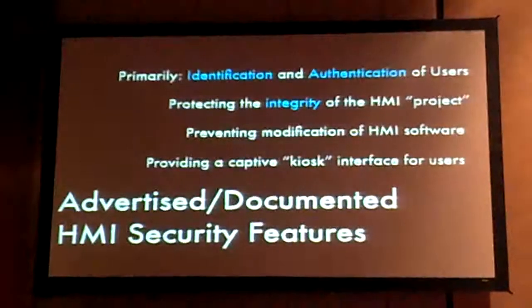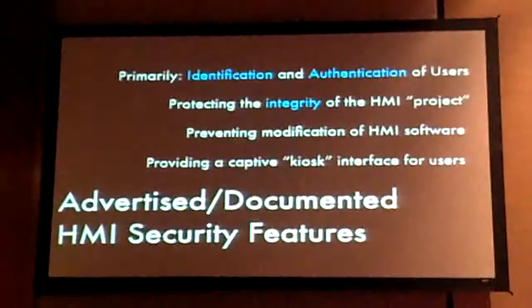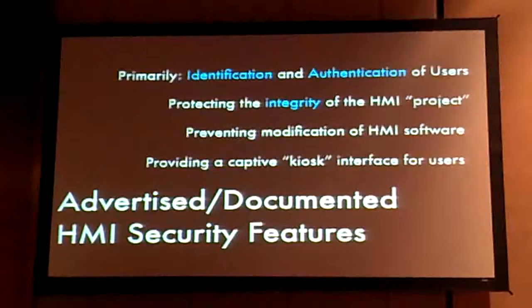But there are a lot of packages that claim some security functionality. Primarily, the security functionality advertised by these products is the identification and authentication of users. There are complex systems for having multiple layers of access — different access levels — from the operators sitting at the control panel all the way up to engineers who can change the code and modify the HMI. The idea is protecting the integrity of the HMI project, preventing modification of the HMI software itself, and locking users into a kiosk interface.